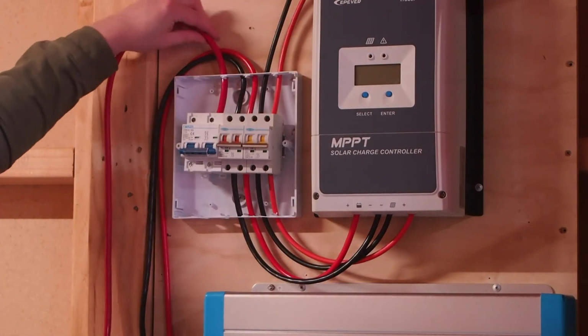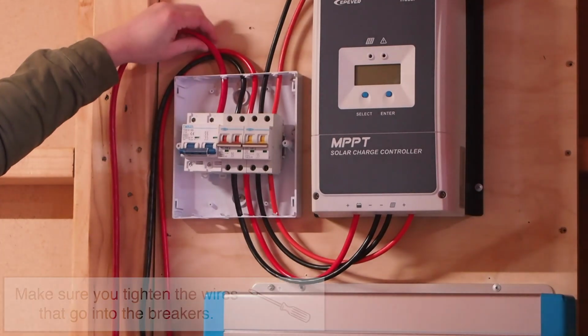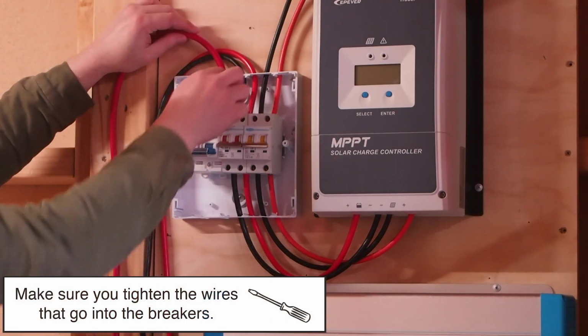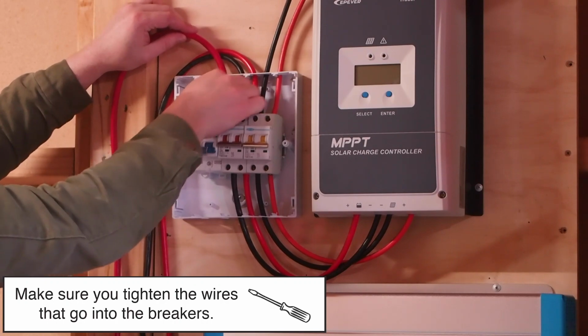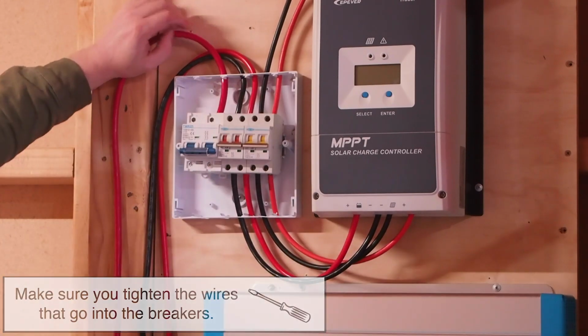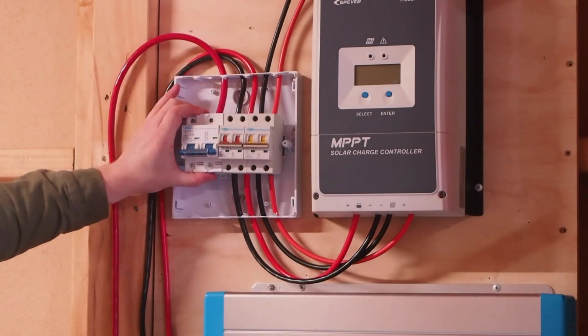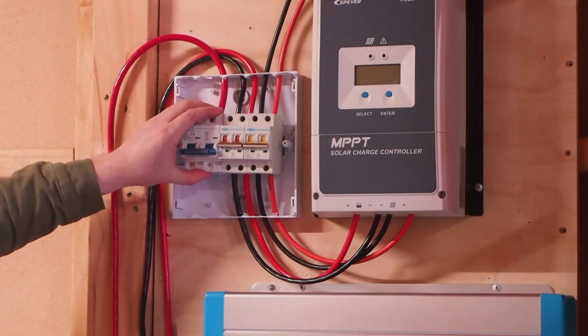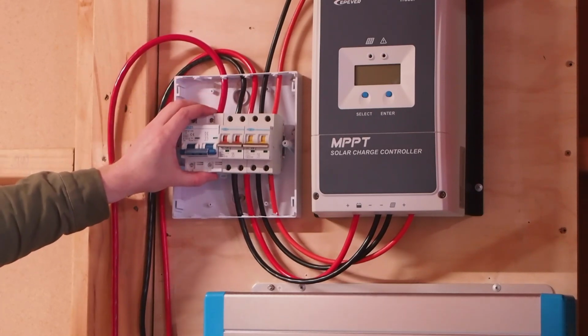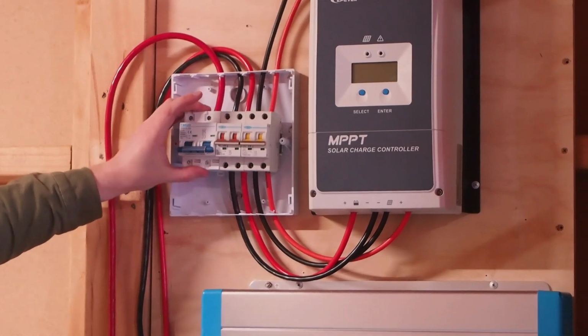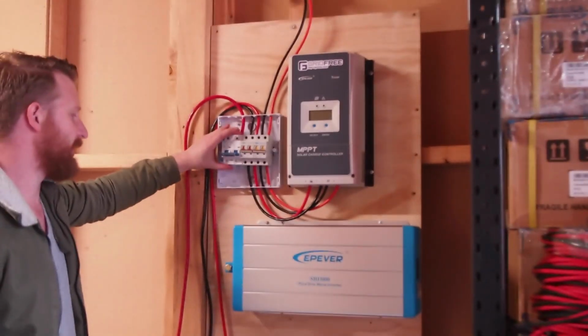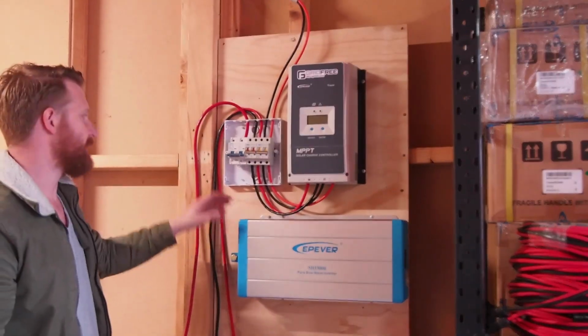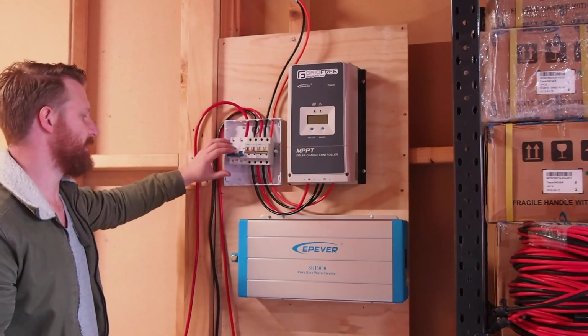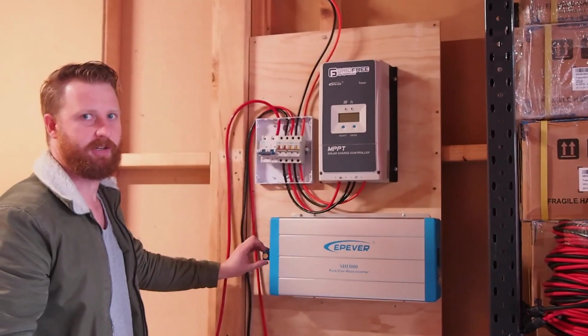When you're clamping in this larger 125 amp cable, you want to make sure that you really tighten down the screw and that this cable is completely secure in the circuit breaker. As this is carrying a high current, you don't want this connection to be loose at all, because if there's any high resistance in this connection, it can generate a lot of heat and either damage the circuit breaker, damage the cable, or damage the inverter. So when you're clamping this cable down into the circuit breaker and the inverter, you want to make sure that you get it as tight as you can.